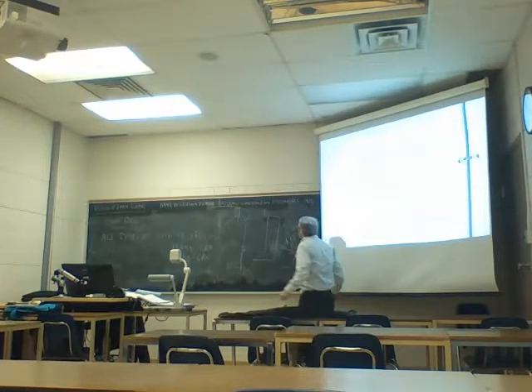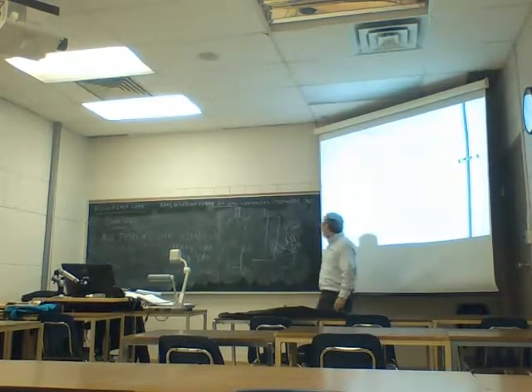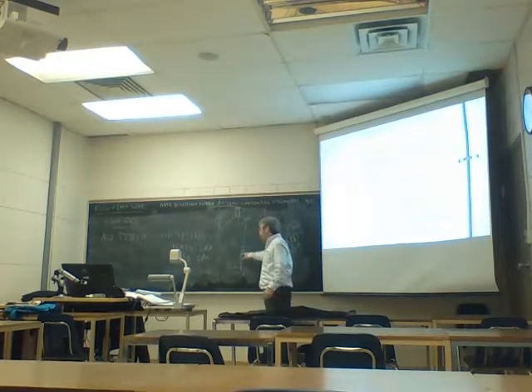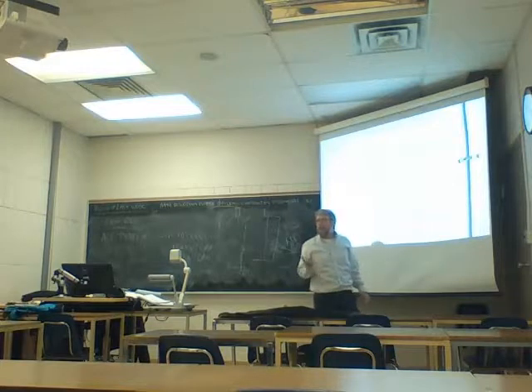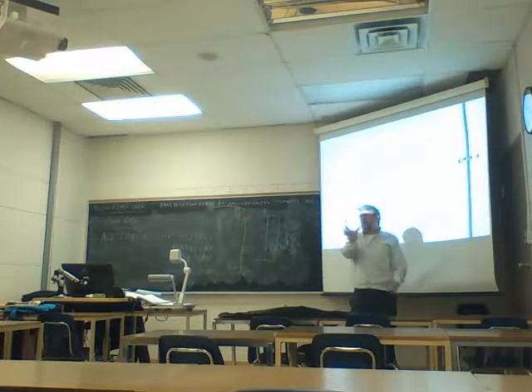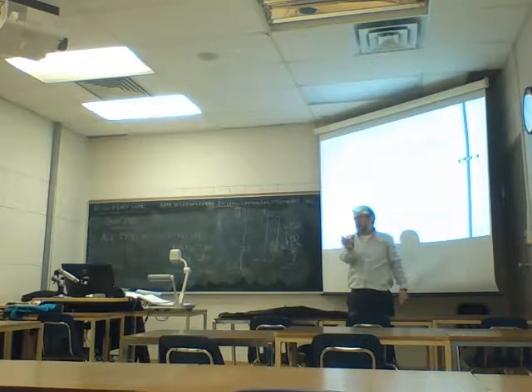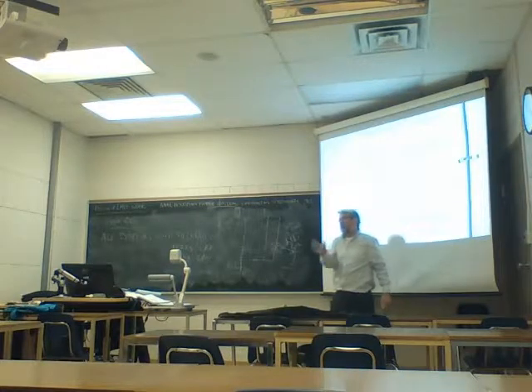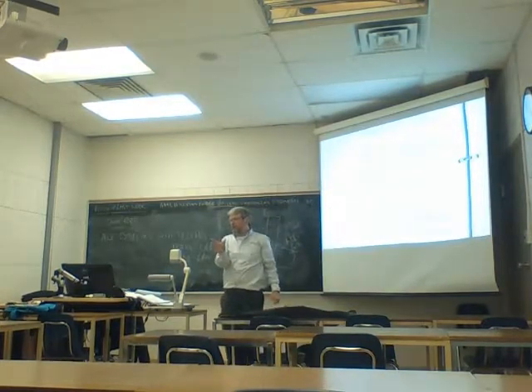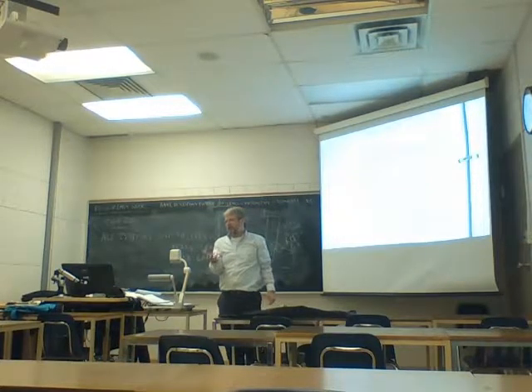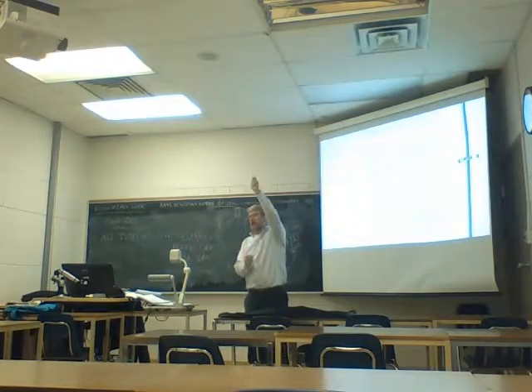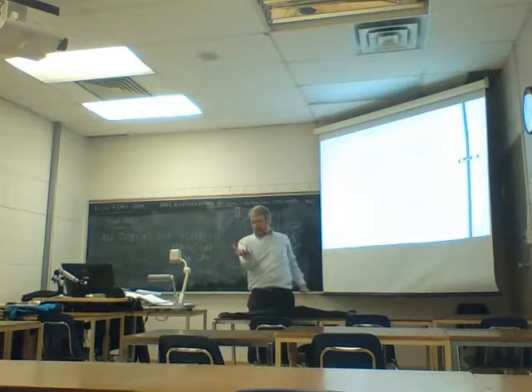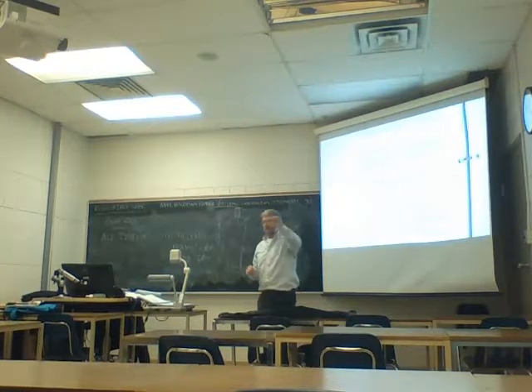If it was only on a vertical line, what can happen from the top all the way down to that valve? Could you get an obstruction a lot easier on a line that's vertical? Yes, a lot easier than a line that's horizontal. That's because you're going to have pressure. The whole idea is that if it's on a vertical line, it can be all plugged full of crap, but there's a lot of pressure behind this. So if it's on a horizontal line, when you open that valve, chances are it's going to pull the crap out of it. That's why they do it.